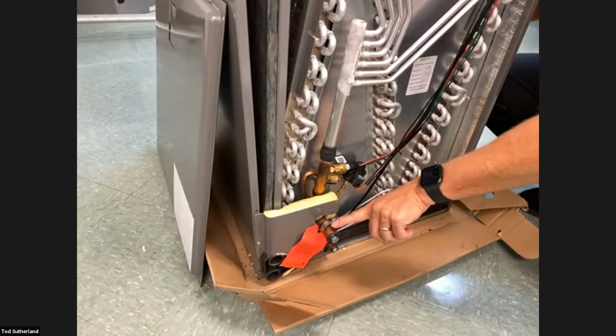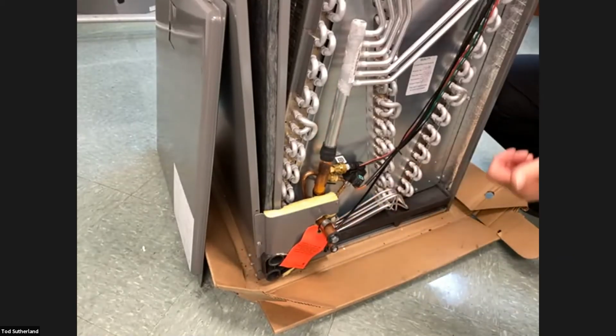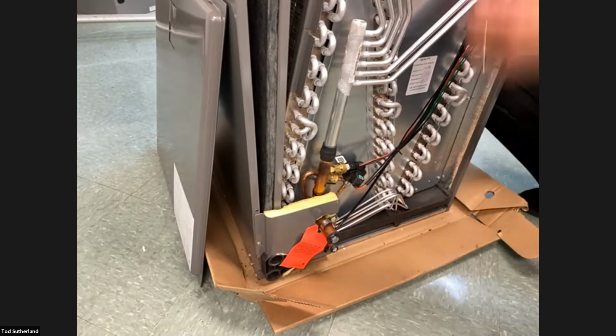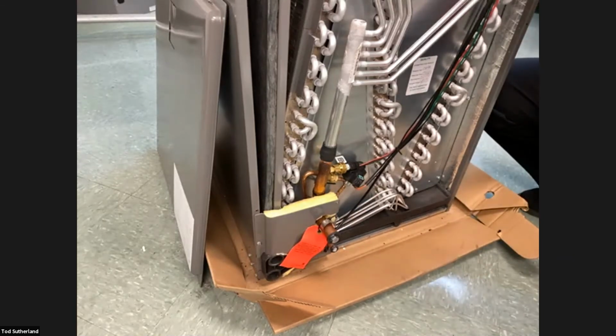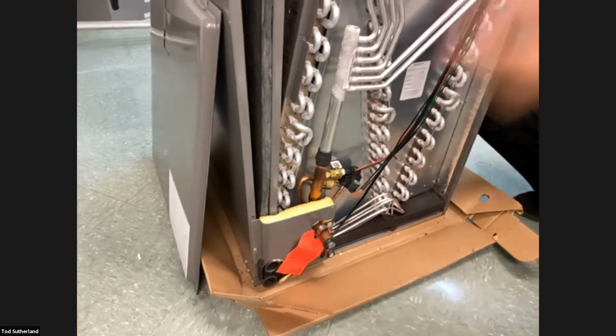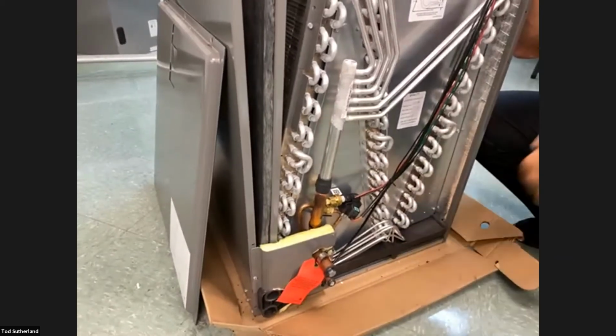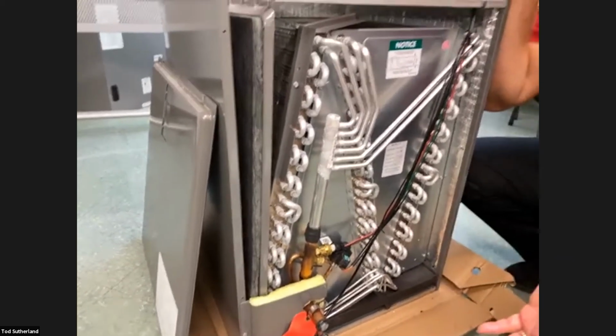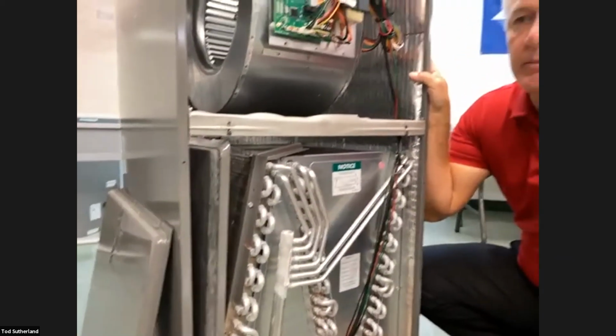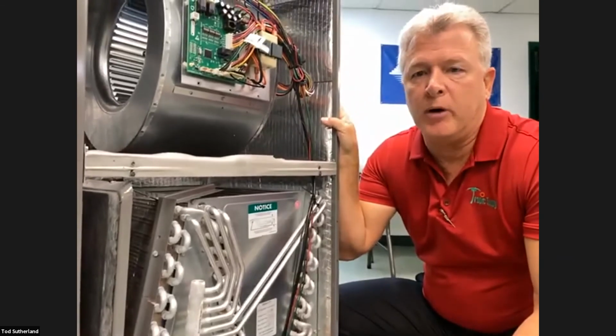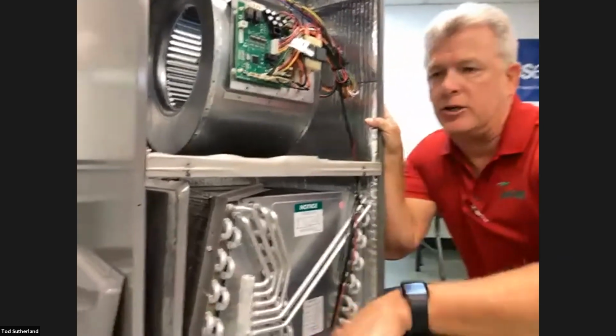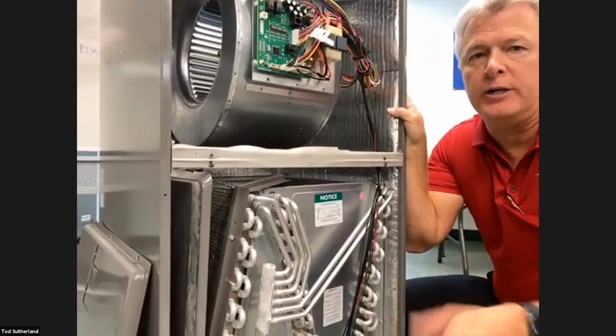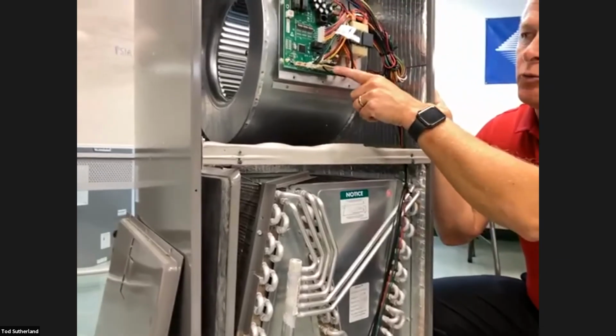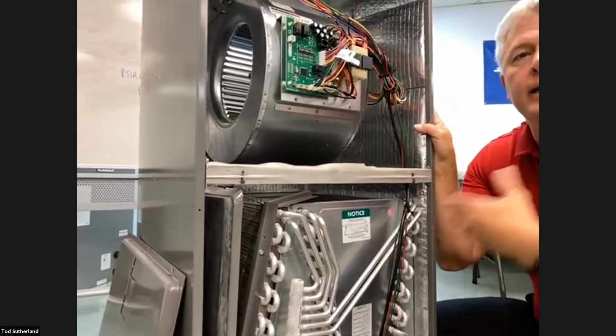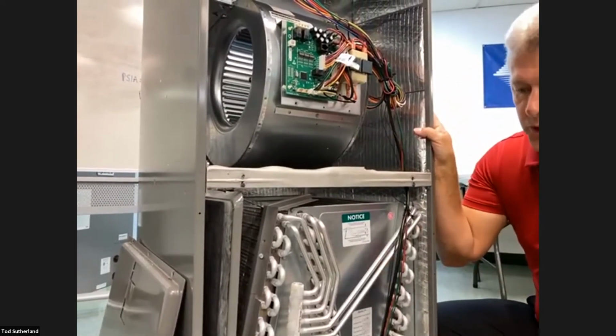There's a couple ways you can test this thermistor. One, you're going to use your ohm meter, pull it off the board and ohm it out and make sure that it's reading close to what you have on your pipe temperature. If you want to see if it's fluctuating properly, just like sometimes we do with regular expansion valve bulbs, you can take this and stir it in some ice water, get it down to 32 degrees, and see that it's reading the proper ohms that you would read at 32 degrees on a 10K ohm scale.